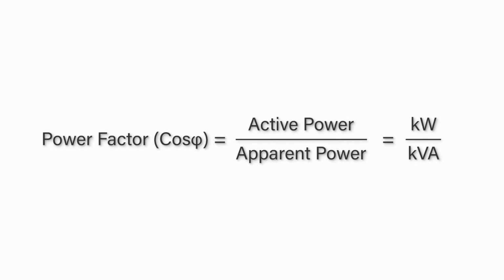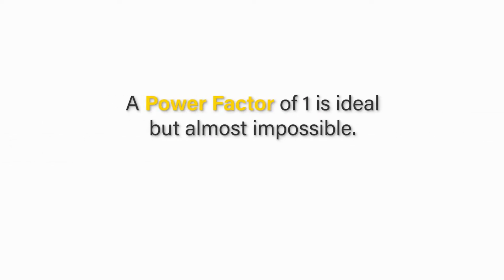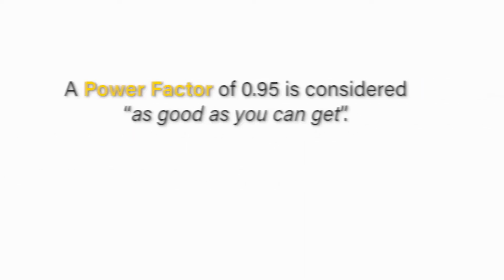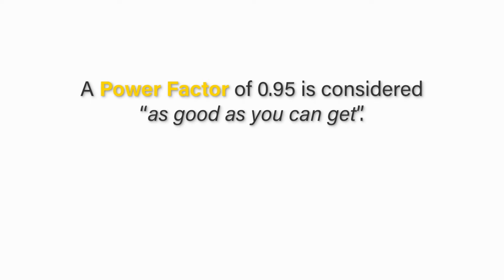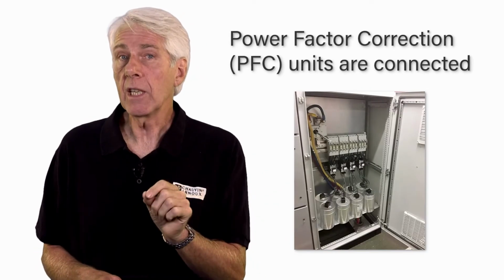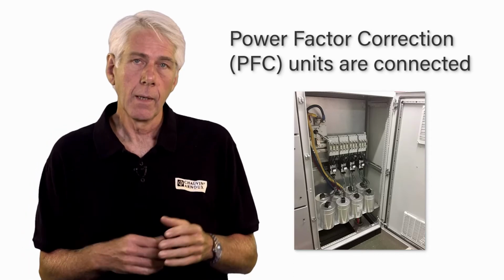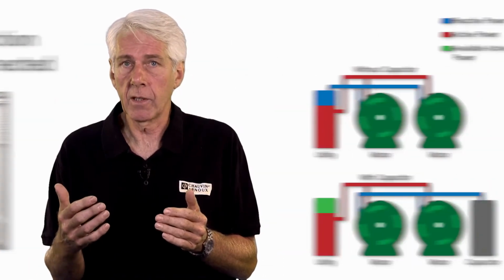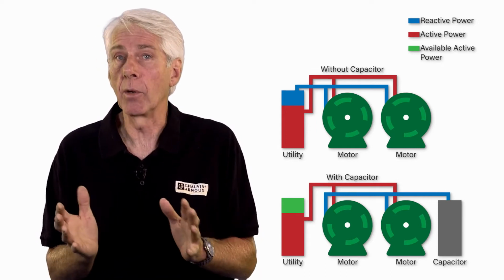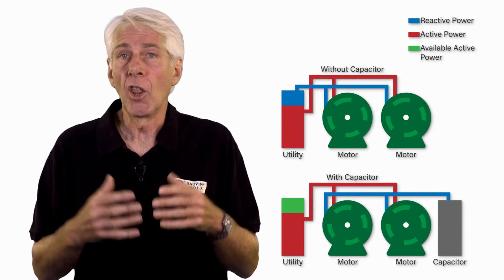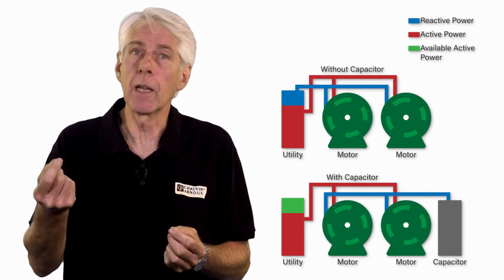Power factor is the ratio of the active power to apparent power, and is used as an indication of how efficiently power is being delivered to the loads in an industrial or commercial site. A power factor of 1 is ideal, but almost impossible. It's like a beer with no froth. A power factor of 0.95 is generally accepted as being as good as you can get, and something to aim for. And this would be a beer with a perfect amount of froth on it. Now, to achieve this, power factor correction or PFC units are connected to the installation. In its simplest form, this consists of a selection of capacitors of calculated values that automatically switch in and out as changes in the operating load require. The capacitance basically counteracts the effects of the inductance in the load.